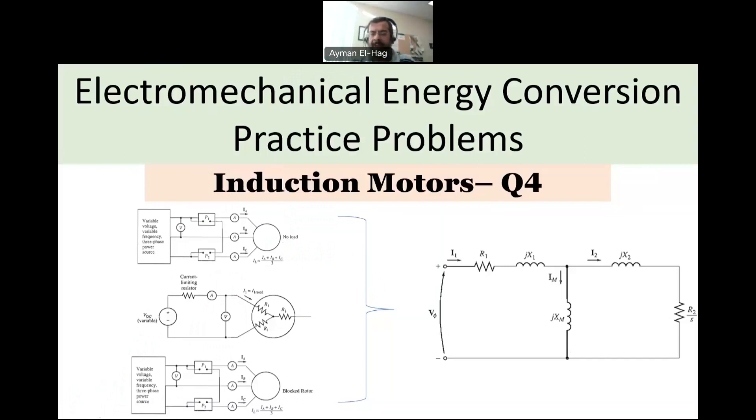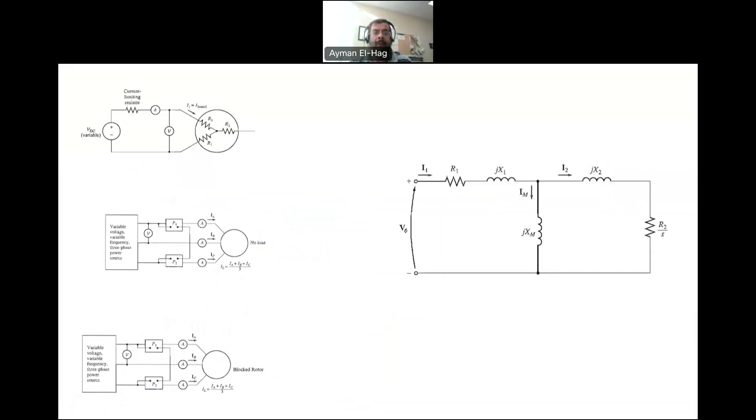For the DC test, it will give us R1. As you can see here, this is a Y connection, so we have two of the resistors in series. We apply DC voltage, measure the current, and using Ohm's law, we will be able to find R1 from this test.